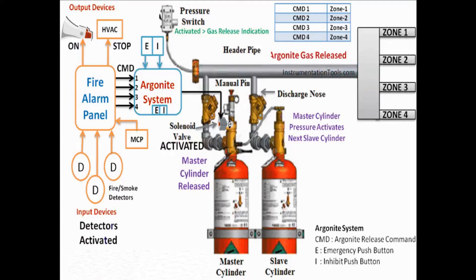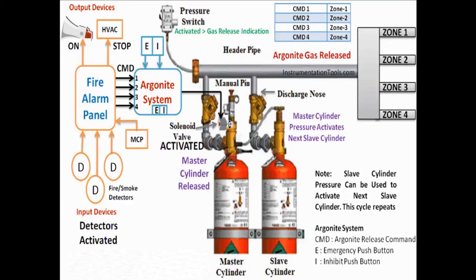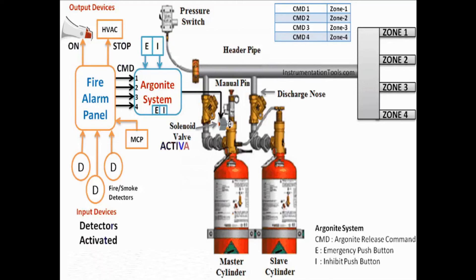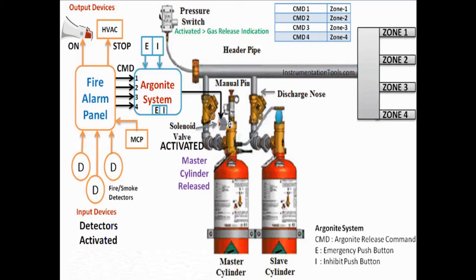Generally we use more than one master cylinder either to speed up the operation or to divide the cylinder quantity to specific zones. A manual valve or release cutter pin is provided on all master cylinders. In case of auto failure, this manual valve can be used to release the master cylinder, which then activates the remaining slave cylinders. Emergency push buttons are also installed near the argonite system or respective zones, and are provided on the argonite panel as shown in the animation.